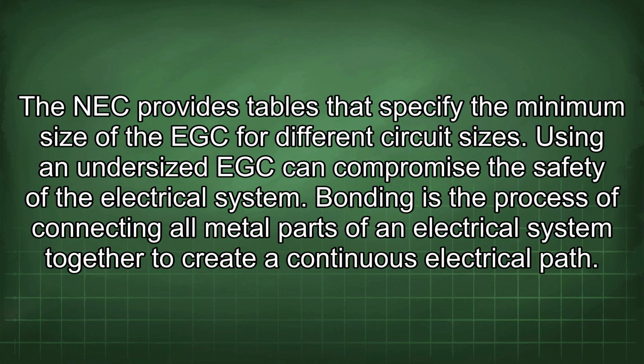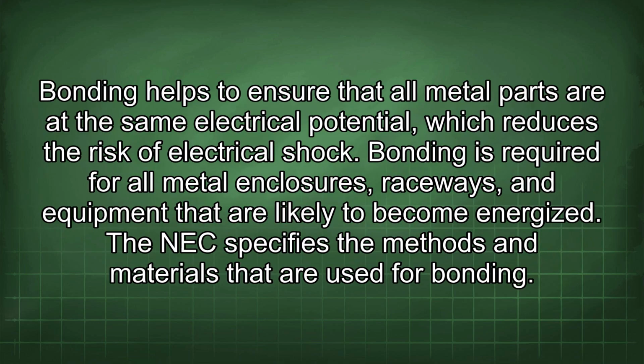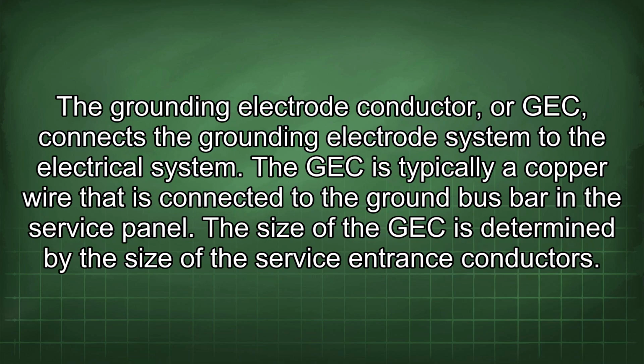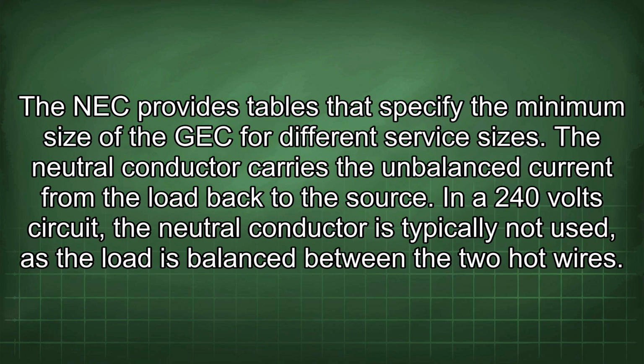Bonding is the process of connecting all metal parts of an electrical system together to create a continuous electrical path. Bonding helps to ensure that all metal parts are at the same electrical potential, which reduces the risk of electrical shock. Bonding is required for all metal enclosures, raceways, and equipment that are likely to become energized. The NEC specifies the methods and materials that are used for bonding. The grounding electrode conductor, or GEC, connects the grounding electrode system to the electrical system. The GEC is typically a copper wire that is connected to the ground bus bar in the service panel. The size of the GEC is determined by the size of the service entrance conductors. The NEC provides tables that specify the minimum size of the GEC for different service sizes.